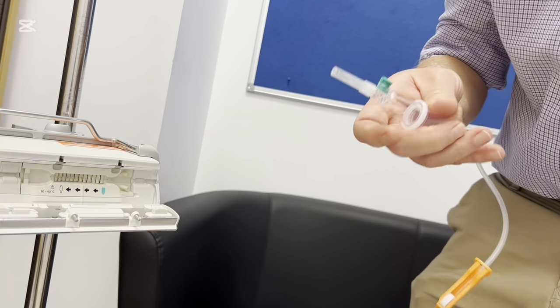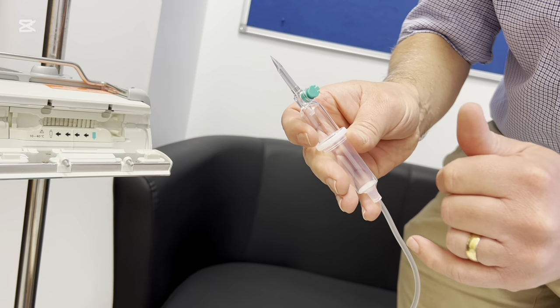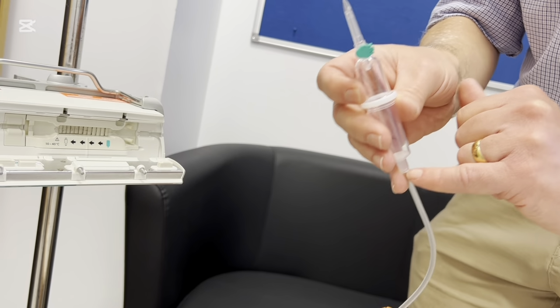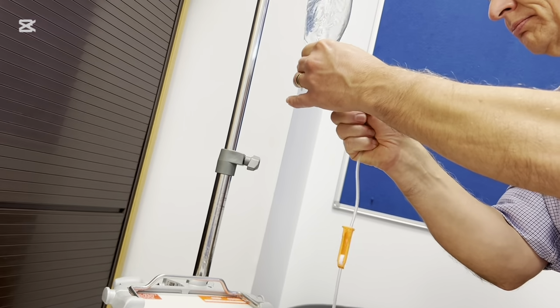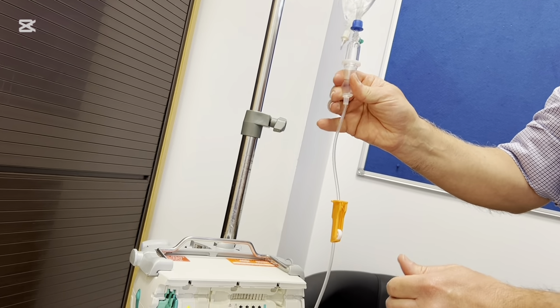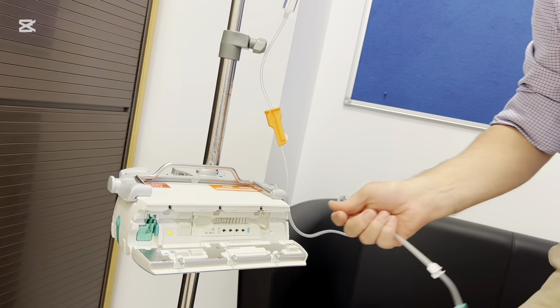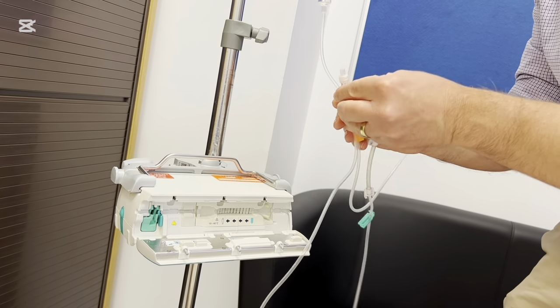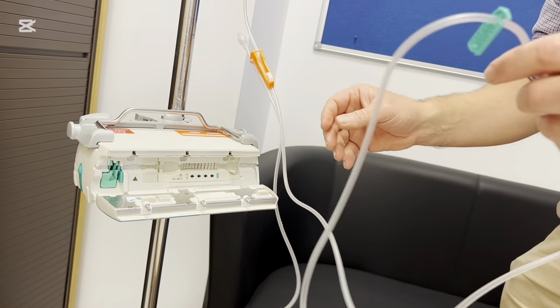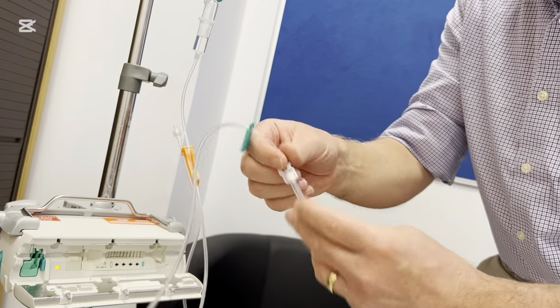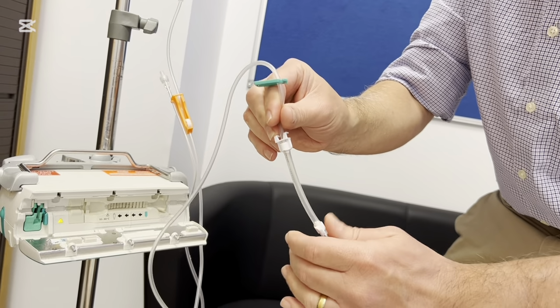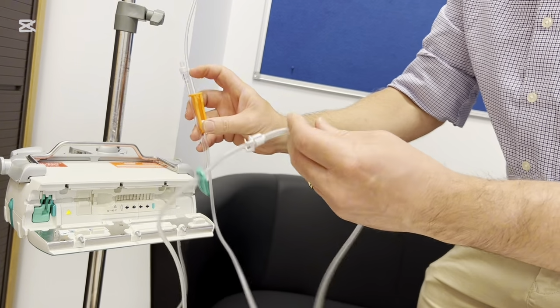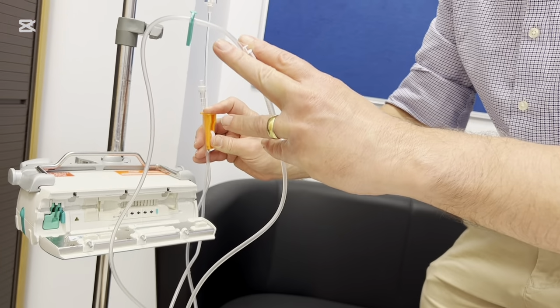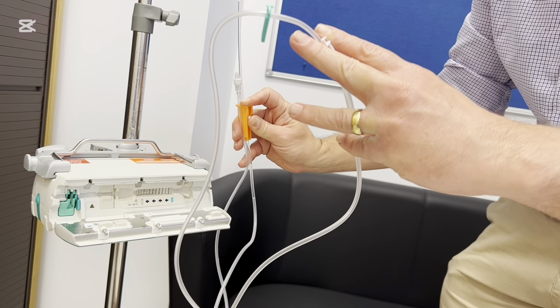And again, as with any consumable device, close the roller clamp first and foremost. You have an air inlet on the administration set and a filter at the bottom of it. Spike the bag, prime the chamber, attach the tubing into the roller clamp. One of the important things on this device is to invert the pumping segment so that it fills from the bottom, so that you don't get air within the pumping segment. So prime this set.